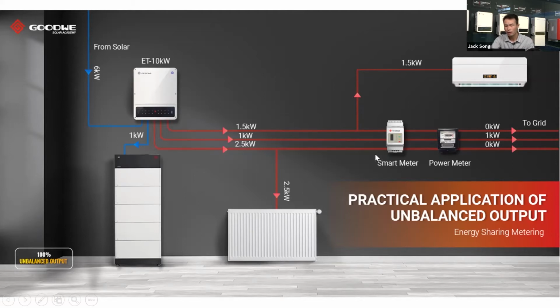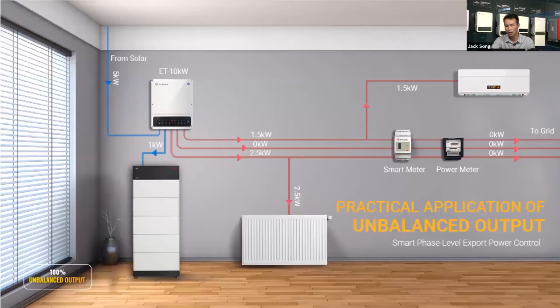All the hybrid inverters, three-phase and single-phase, can work in many scenarios for self-use and export power limit. But the three-phase ones are used in three-phase house grid systems, especially for zero export with phase level zero export, which I've introduced. This is also a scenario about phase level zero export. It means that on each phase, the export power limit has to be 0.